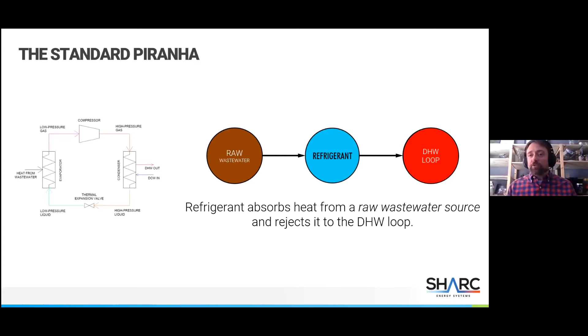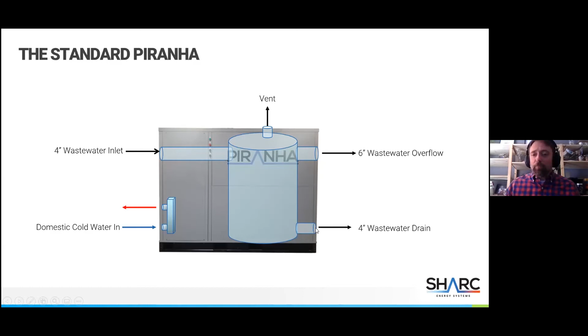Really, when you're taking a look at the PIRANHA itself, it's got simple connections to it. You've got your wastewater inlet. Internally, there is a tank, and that tank is actually our evaporator coil that allows us to extract the energy from raw wastewater and transfer it into the refrigerant loop. So that tank then fills up with the raw wastewater. As it fills completely, there's an overflow. As we drain the energy from that raw wastewater and transfer it to the domestic hot water loop, it is then drained out to the sanitary sewer.